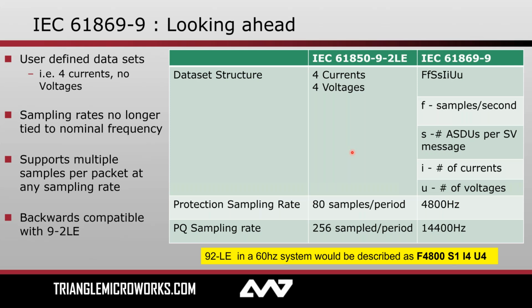So the key differences are what I want to highlight. The first one is that it's now user defined. What if I only want to measure current? What if I don't care about voltage? In that scenario, I can have a user-defined data set that says I only want 3 currents or 6 currents, but I don't want any voltages. Additionally, sampling rate is no longer tied to nominal frequency. There are a couple of recommended sampling rates for most protection applications. You'll be using this 4,800, which is the same number, you might notice, that we had in a 60 hertz system. So not a whole lot changed there.